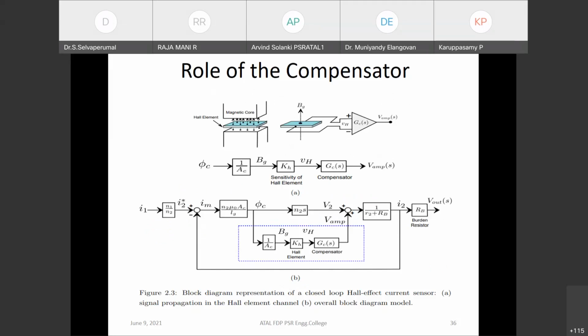For accurate measurement of I1, the secondary current I2 should ideally equal n1 by n2 into I1. In other words, the magnetizing current Im, and hence the core flux phi C, should be brought down close to zero. The role of the compensator Gc(s) may be understood from the equivalent circuit shown previously: the voltage source Vamp is a function of VH and Gc(s), as expressed in equation 2.7.